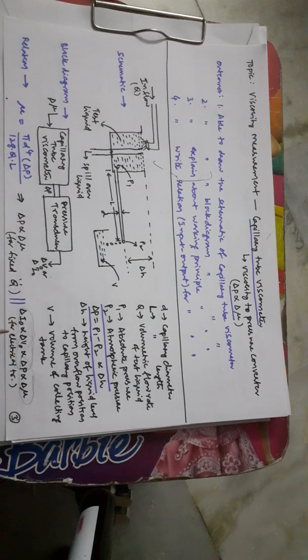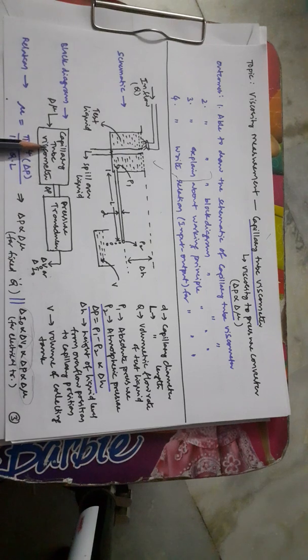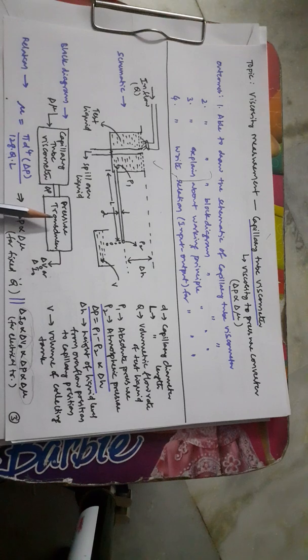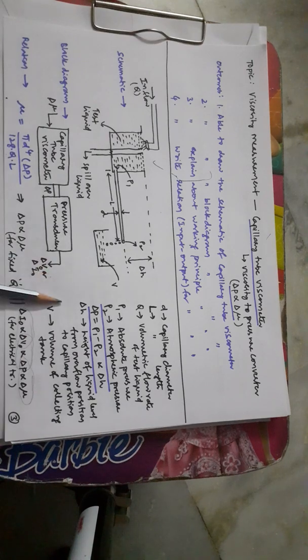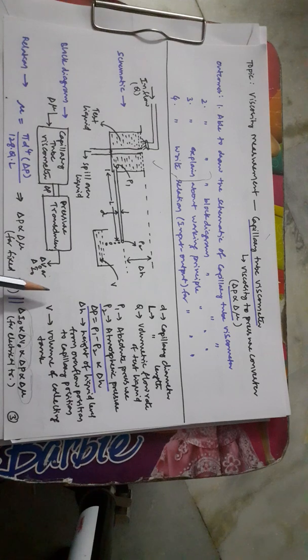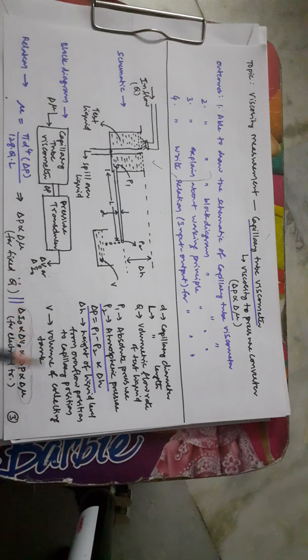In the block diagram: the first block is the capillary viscometer converting delta mu to delta P; the second block is a differential pressure transducer converting delta P to a voltage; and the third block is a V-to-I converter producing a current output. The final electrical output — either voltage or current — is proportional to the input viscosity.